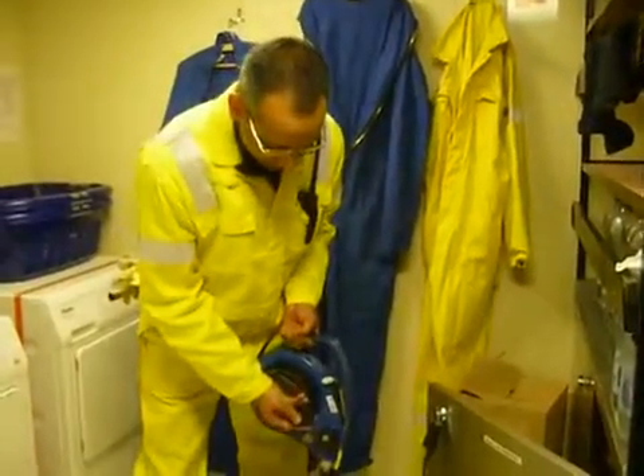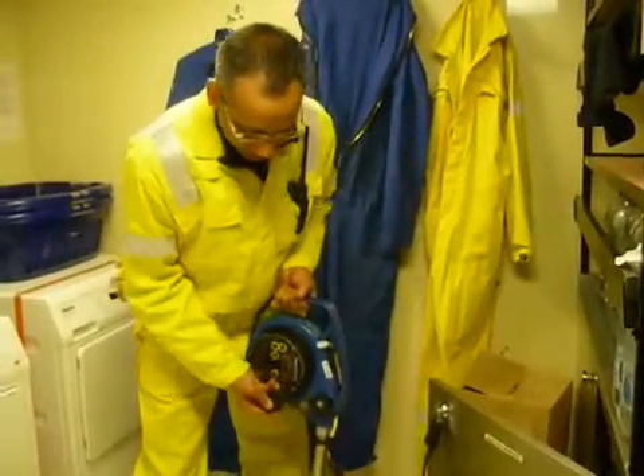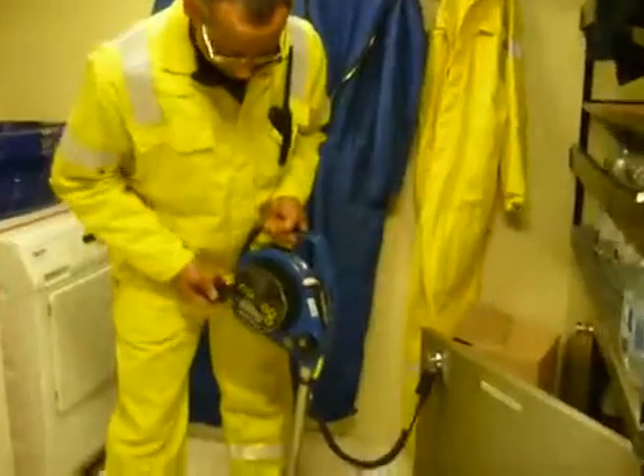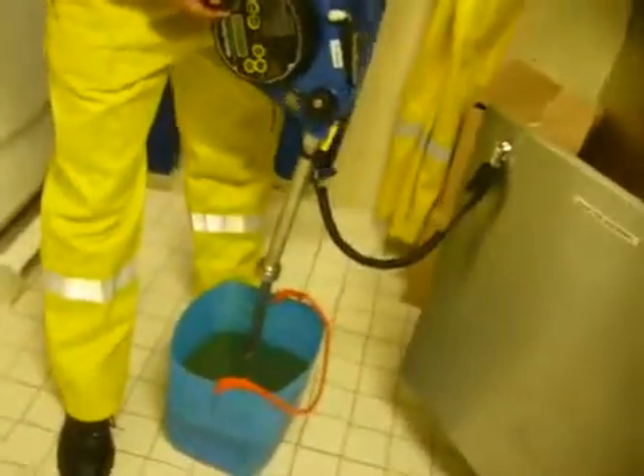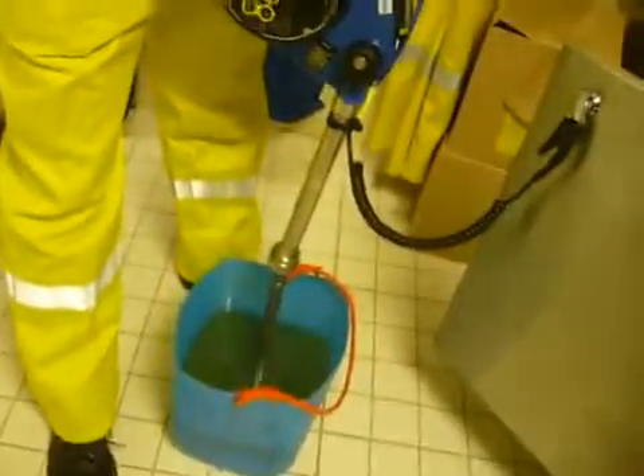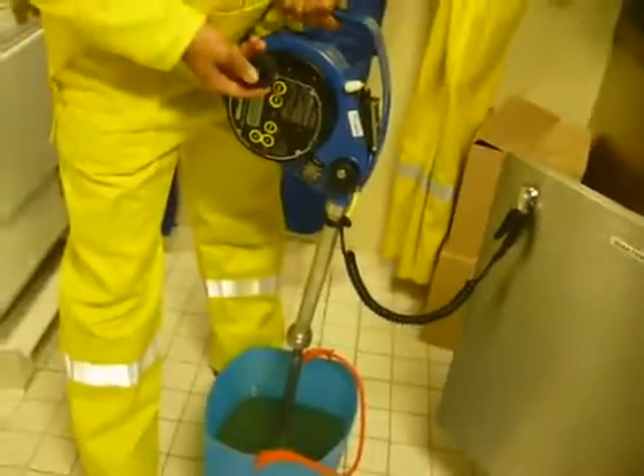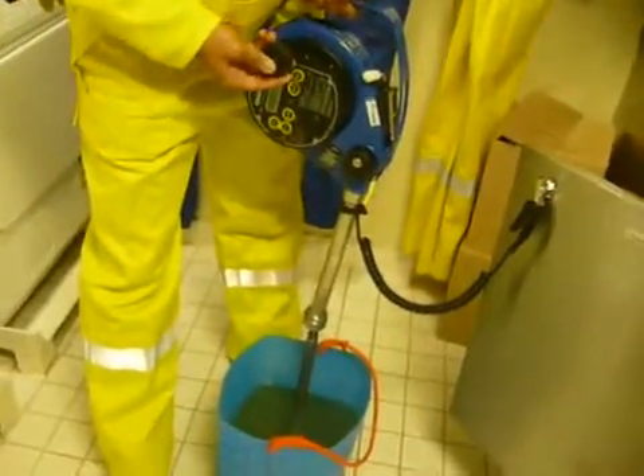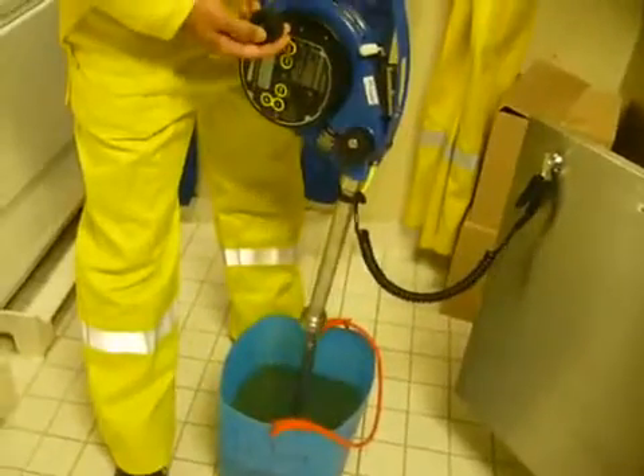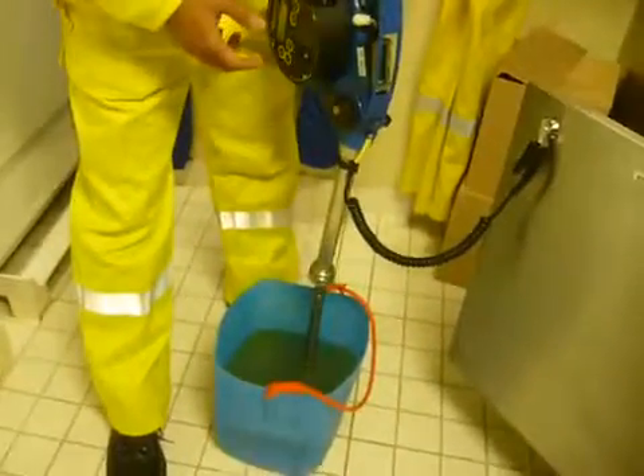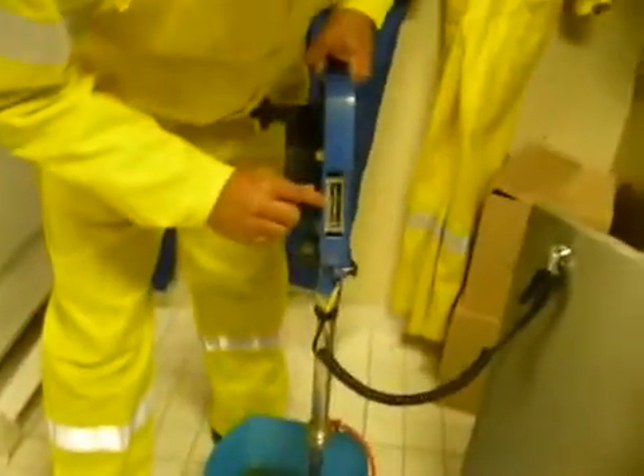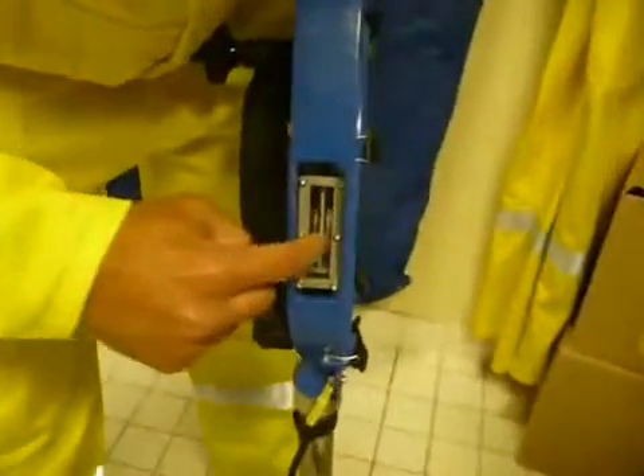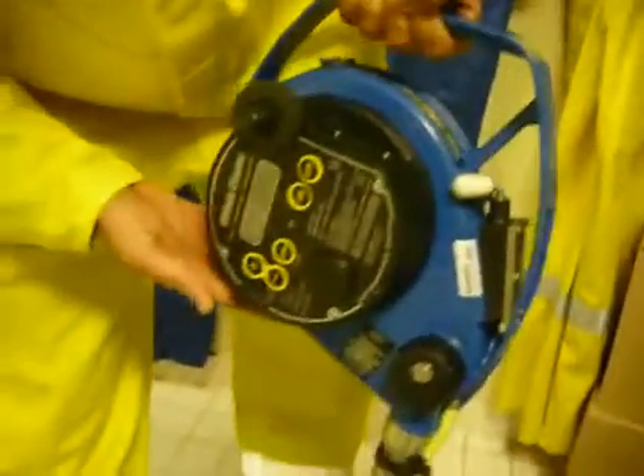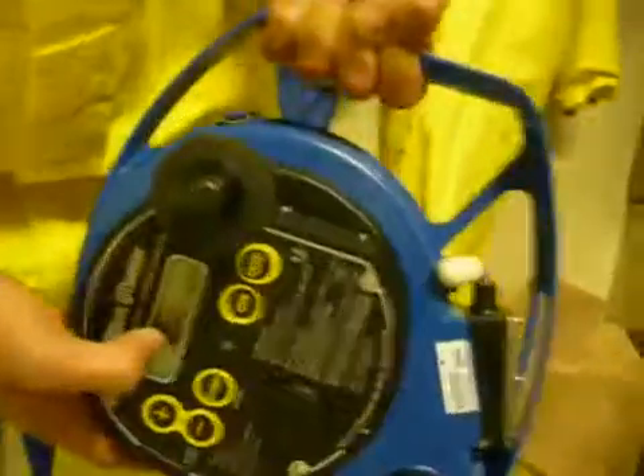So we will start lowering the probe, and you can see the probe will go down and it will change the sound. Now this is the level of the hydrocarbon in the tank, and here you can make out the ullage. You can read the ullage from this gauge here inside, and it will also give you the reading here.